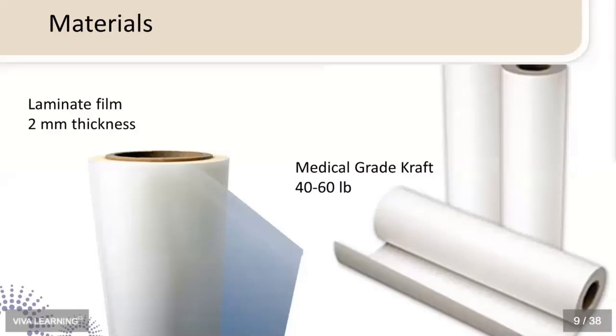Because the porosity, or the holes in the paper that the steam gets through, are about 0.1 microns in size, they're going to open up during the steam presence cycle, and then when the dry cycle begins, those same fibers are going to close those pores so that it creates a barrier to maintain sterility. The kraft paper also doesn't have any chemicals that brighten it and make it look whiter, because you don't want any toxic chemicals released during the sterilization process. This type of fiber also withstands a lot of pressure, because think about the PSI, somewhere between 18 and 27, give or take. That's going to put a lot of pressure on the paper to hold steady during the sterilization process, so it's going to reduce puncture or breaking of those strands. So you want something that's about a 40 to 60 pound weight paper.